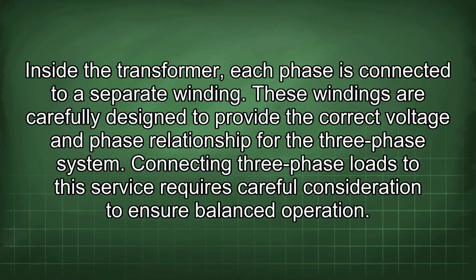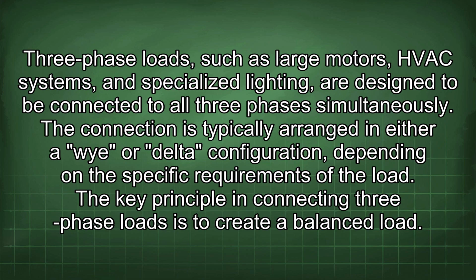Connecting 3-phase loads to this service requires careful consideration to ensure balanced operation. 3-phase loads, such as large motors, HVAC systems, and specialized lighting, are designed to be connected to all 3 phases simultaneously. The connection is typically arranged in either a Y or delta configuration, depending on the specific requirements of the load. The key principle in connecting 3-phase loads is to create a balanced load.